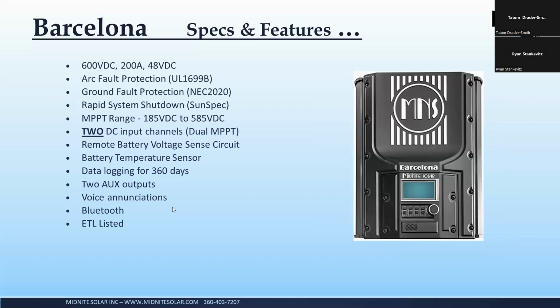There is an upcoming rapid shutdown transmitter for these as well. So if you're required to do rapid shutdown, we have a 600 volt string level SunSpec rapid shutdown device coming to the Canadian market, hopefully here in another 4 to 6 weeks, I think is what I'm being told. That will work with any SunSpec transmitter, but it is string level. It's not module level. Just be aware of that.